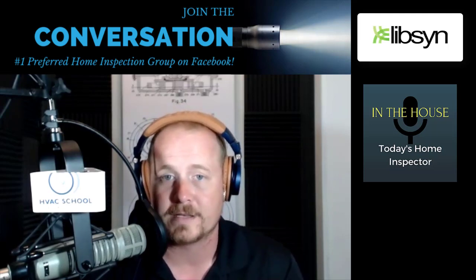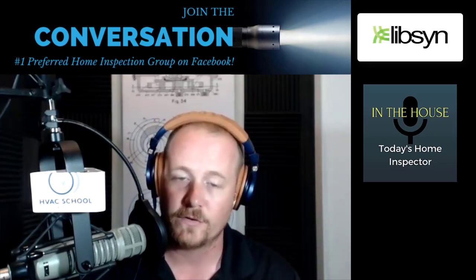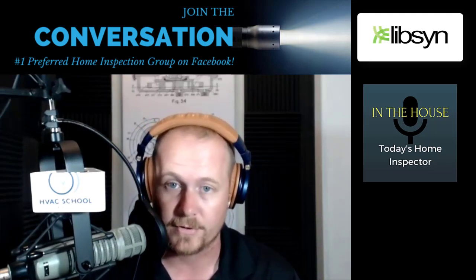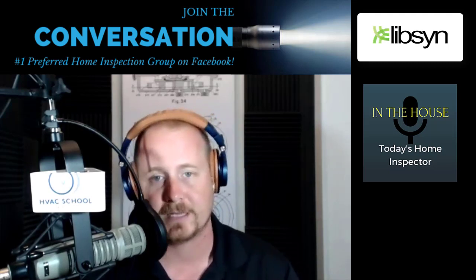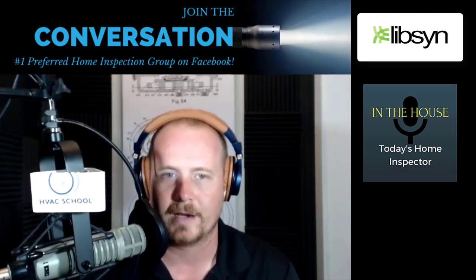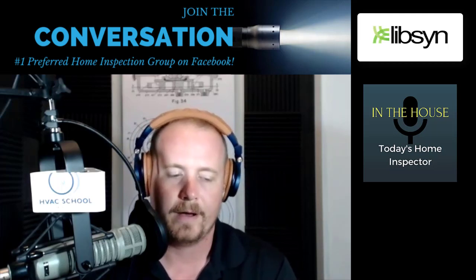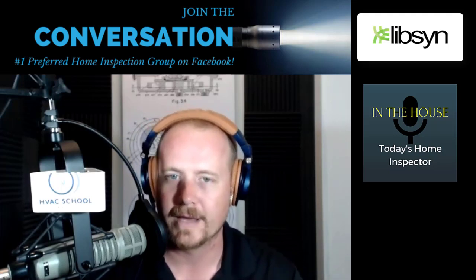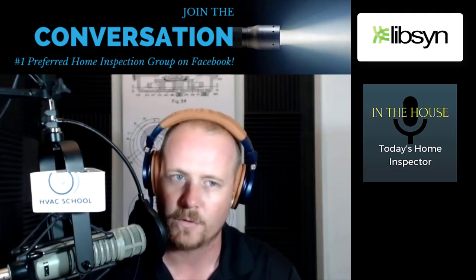And it also varies based on where you live, and that's why if you're listening to me right now and you're in the mountains of Colorado, well, the rules are a little different there. And if you're in a place where you have higher relative humidity and people aren't running 400 CFM per ton, they're running a little lower airflow to pull more humidity out of the air, then your split's going to be a little higher. Most of you are out there working in a particular area, and so you'll start to learn the rules of that area. But if you benchmark against a Delta T calculator for a while until you get the hang of it, that's really going to give you a much better feel.